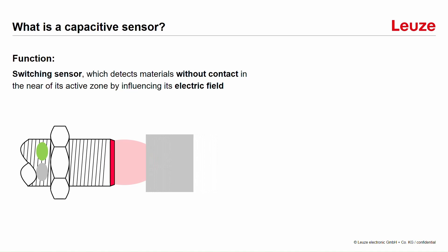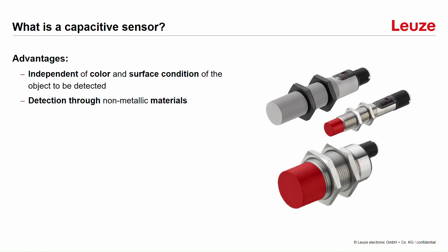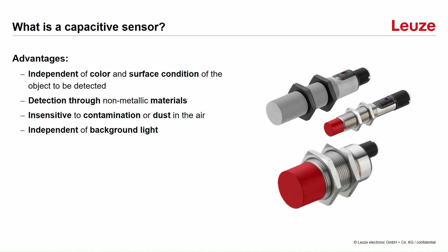You can see this now in a short animation. The main advantages of capacitive sensors are that they are completely independent of the color and also the surface of the detection material. Besides, they are able to detect even through walls under certain conditions. They are also very insensitive to contaminations in the air, for example dust. And what is also very important, they work completely independent of any kind of background light.